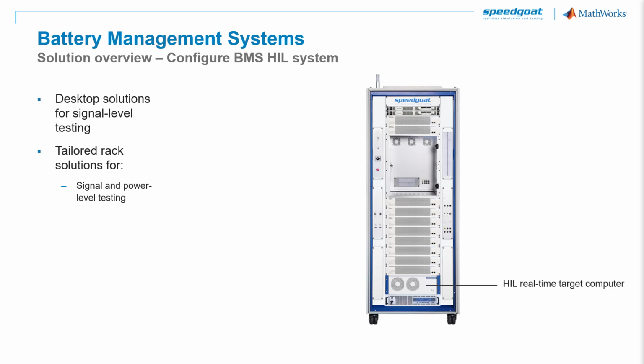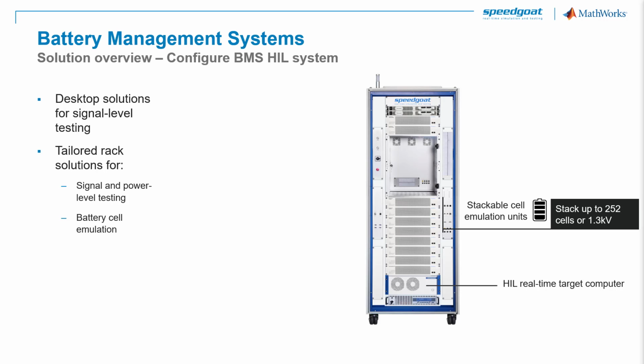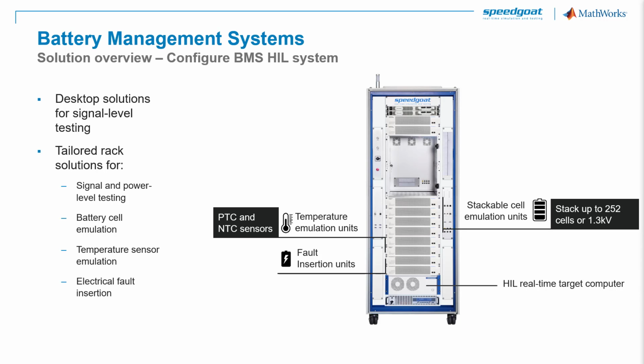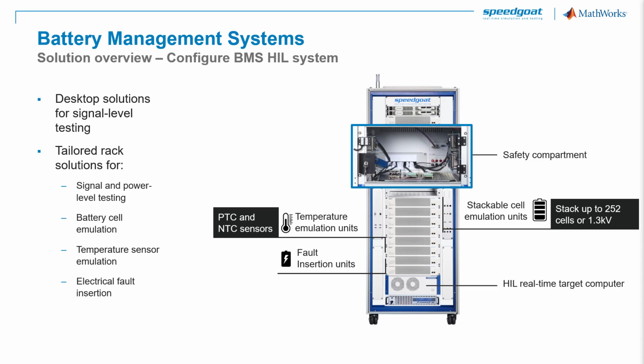In addition to the hardware-in-the-loop simulator, a typical BMS hardware-in-the-loop rig includes these components: a stackable cell emulation unit, or several of them, allowing you to simulate full battery packs with cell-level fidelity. Additional modules allow you to emulate temperature sensors or insert electrical faults if needed. Then a safety compartment for your BMS controller, as well as power supplies that can emulate the high voltage and low voltage battery packs and additional current and voltage probes.